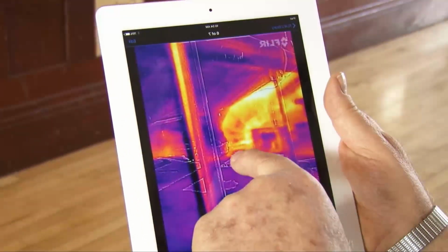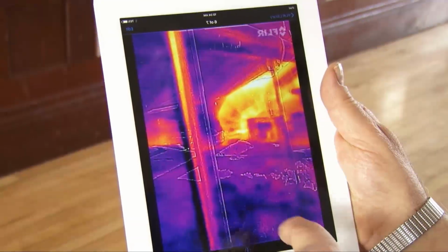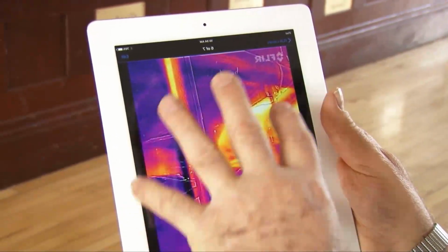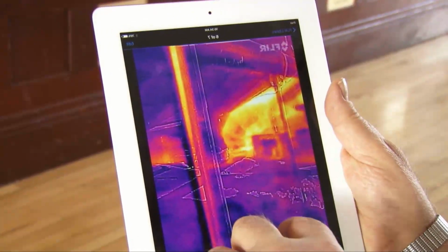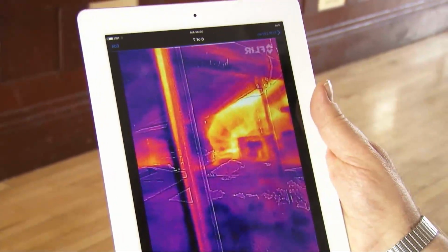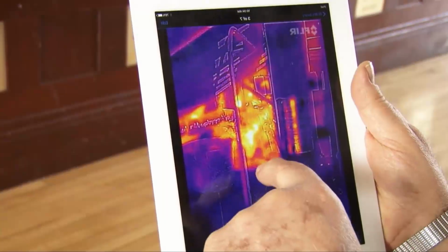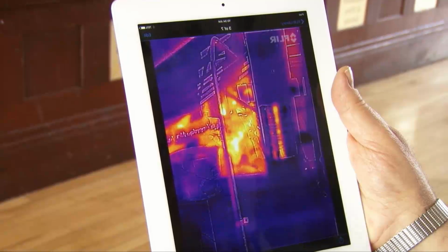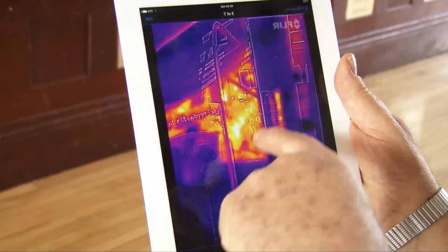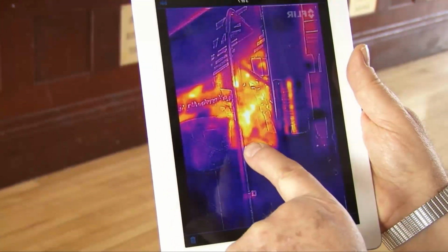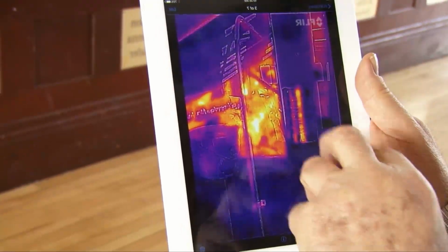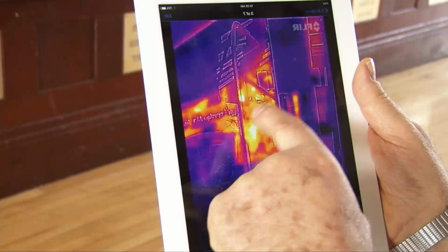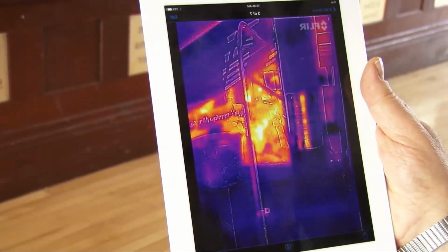We can also see in the attic that we have some duct pipe that is giving off a fair amount of heat into the attic. That should be insulated so that we keep the heat all coming down into the auditorium and not escaping into the attic. This one is a picture looking at the whole row of ductwork up in the attic over the top of the auditorium. In this area is where the pipes are pumping the heat down, but we can see that the ductwork itself isn't insulated very well. We're getting a fair amount of heat loss into the attic right over the heat ducts.